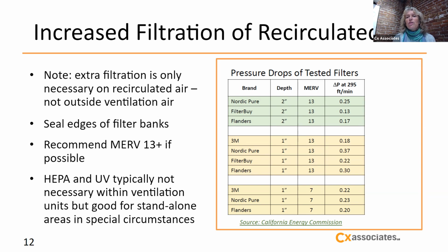HEPA filters are also not recommended for general air handling units because of their pressure drop, and fans aren't designed to handle that much pressure drop. You're going to cut your airflow drastically if you put a HEPA filter in there, and that goes against what we're trying to do here. We're trying to get enough turnover to keep things moving, and a HEPA filter would be a problem for that. So we typically don't recommend putting them in air handling units, but HEPA filters and even UV light are good as standalone devices in special circumstances.